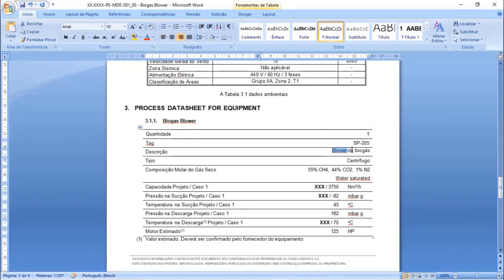So we have the tag, we have the description, we have the type of equipment, because it is a blower, but if it was a compressor, it would be a centrifugal compressor or a positive displacement one. And we need to inform the gas composition. And here we will inform the new flow that is around 3,333 cubic meters, because we split that in three, and the new suction pressure is -161.7. You will get this information from your process flow diagram. The suction temperature will be the same, and the discharge pressure will be the same also.